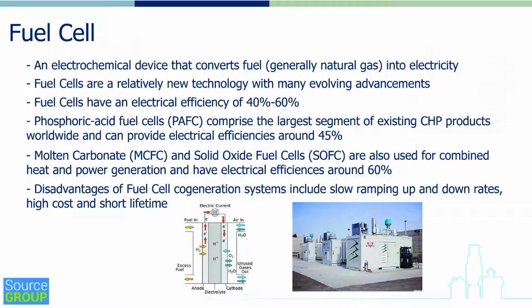Disadvantages of fuel cell cogeneration systems include slow ramping up and down rates. And what that means is that if the electrical demand is going up and down and you want to follow it, the fuel cell may have trouble adjusting rapidly enough to meet those demands. And they are higher cost with a shorter lifetime.